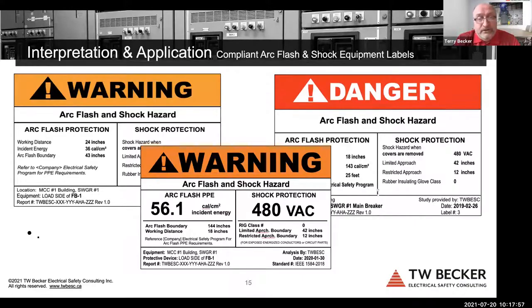These are compliant labels. The one on the bottom is the latest derivation. I've just increased the size of the incident energy value and the size of the voltage on the label that you see on the top left, because these labels print out 4x6 and the print's very small. And we want the qualified electrical worker, the task qualified worker, to focus in on that incident energy value and focus in on the voltage for shock. And then they determine arc flash PPE with an arc rating, right? An arc thermal performance value that's equal to or greater than the incident energy on the label, not a category number, an ATPV on the label of the PPE.